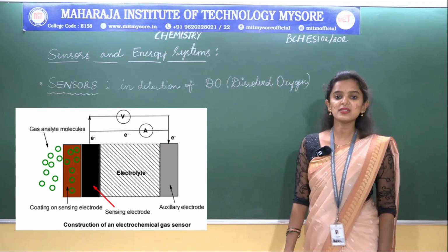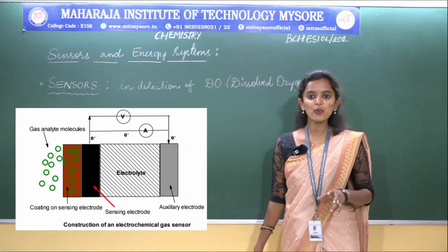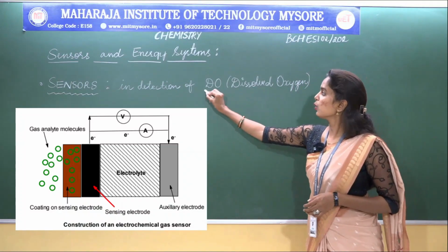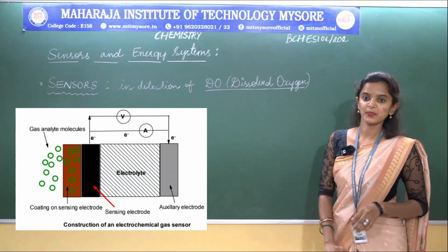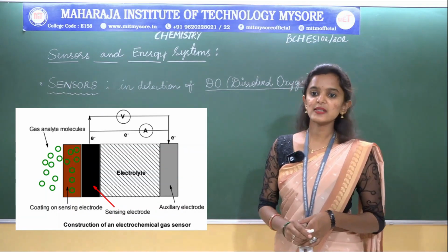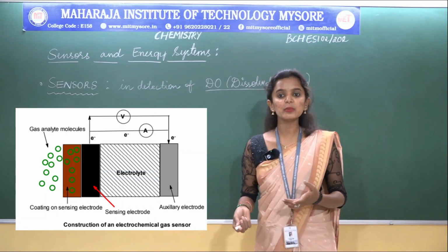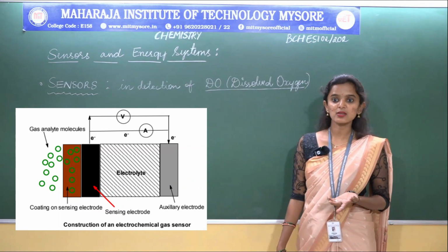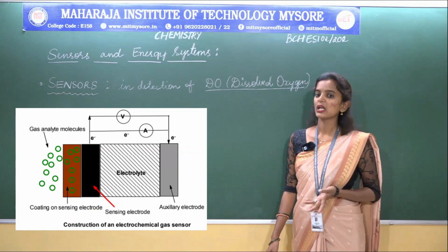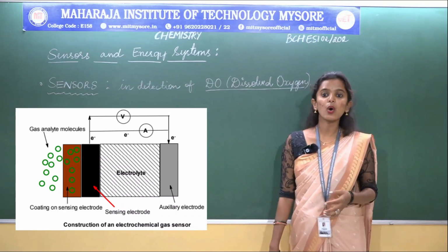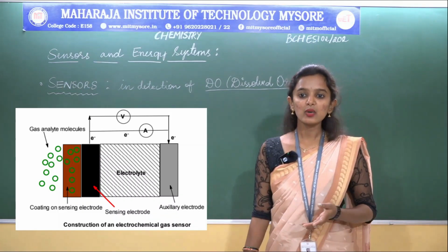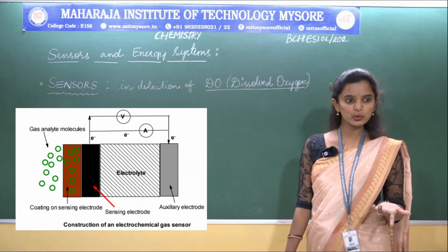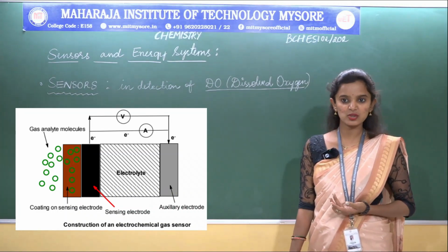The oxygen present in water in its dissolved form is called DO or dissolved oxygen. Electrochemical sensors which are used in the measurement of DO are called amperometric sensors or Clark type sensors, and galvanic sensors are also used in the measurement of dissolved oxygen.